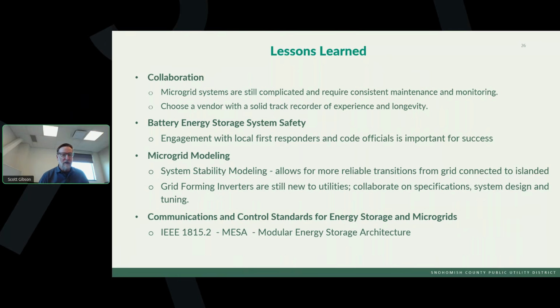Microgrid modeling is another lesson - I think we're still figuring out the best way to model these things and make sure they can interact with the grid without causing problems. All utilities are still struggling with that a bit, and grid forming inverters are still relatively new. Vendors are still having some issues with grid forming, just making sure they're stable on the grid, so you've got to pick a good vendor willing to stick with you while you iron out the issues.